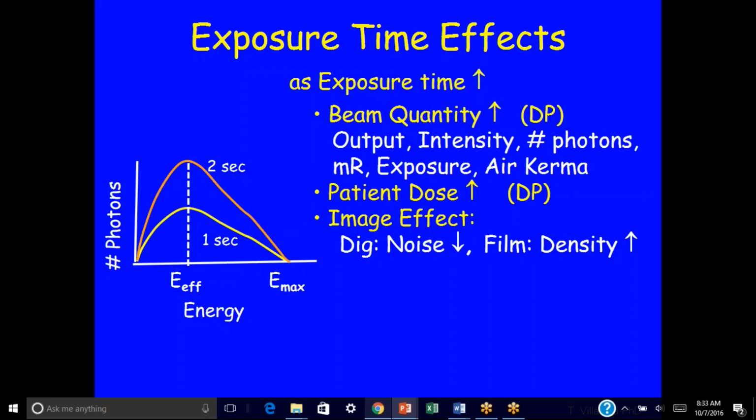Now, here is what has been experienced when we first went to digital. It's pretty much under control these days, but when we first went to digital, what was observed was what we call dose creep. I understand that that term was used in two board questions 2 years ago on the boards. This is what that's all about. If you give a little bit more radiation, the image looks better, well, that's positive reinforcement. A tech that gave a little bit more radiation looks at the image and says, hey, this is better than what I was doing before. So now he adopts his techniques to include a little bit more exposure time because the images come out better. You always want to get a better image. But remember, by increasing the exposure time, you also increase the dose.